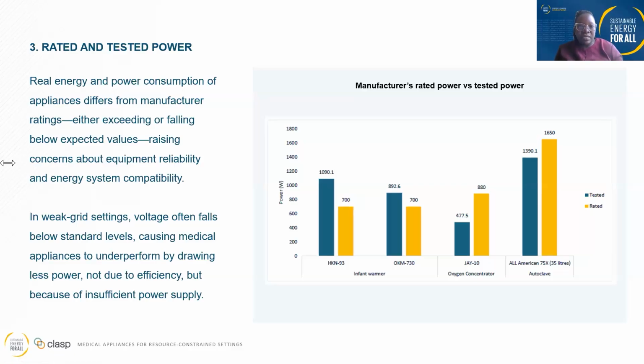For instance, when we tested two different infant warmers of the same brand, both recorded higher consumption levels than indicated on their labels. The difference between rated power and actual power consumption ranged as much as 45% below, or even 56% above, the stated value.